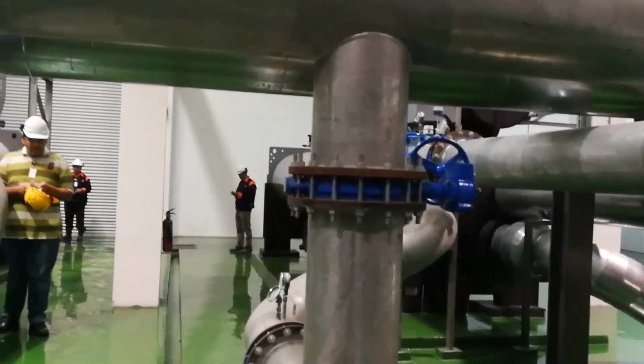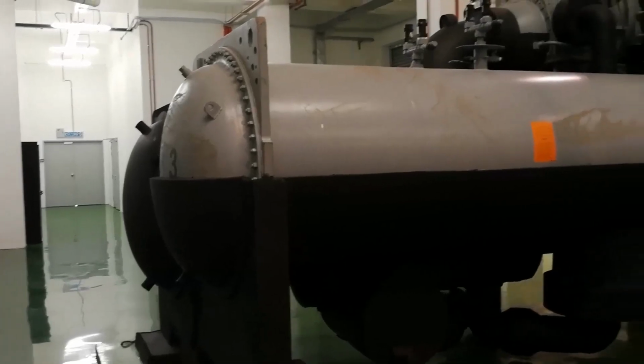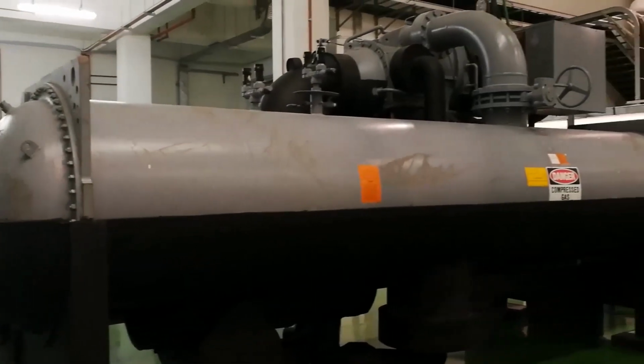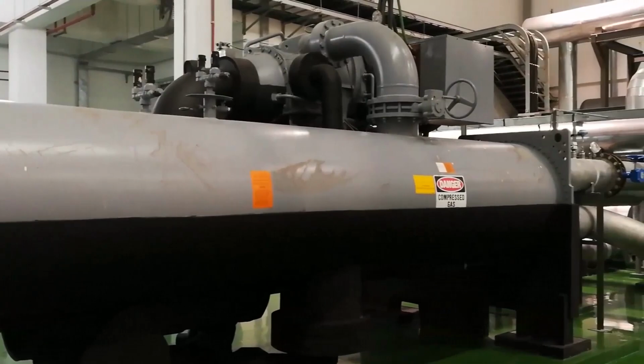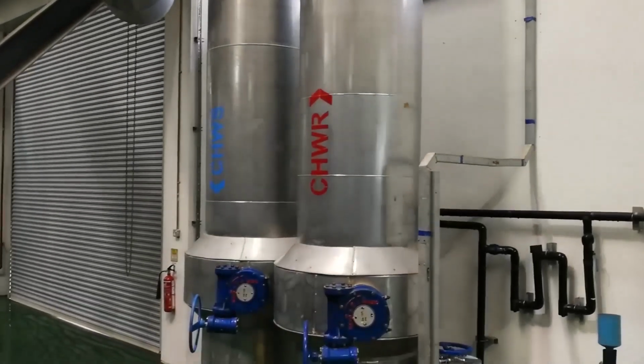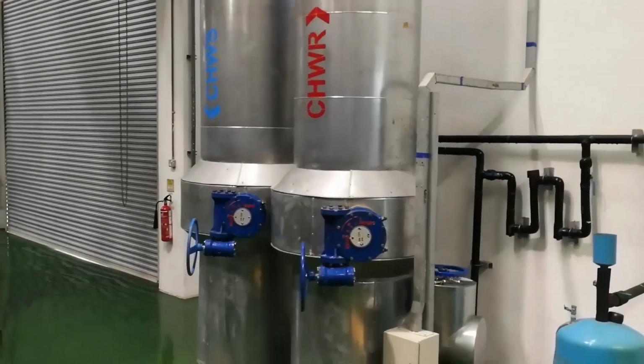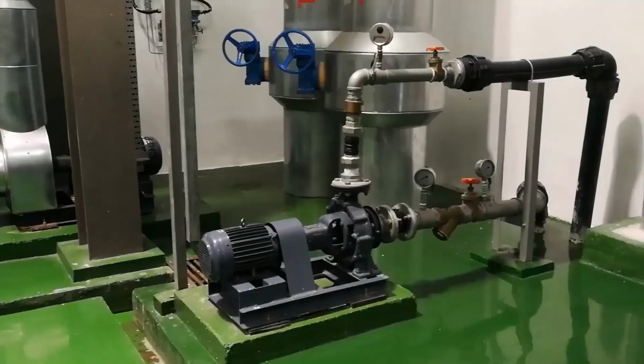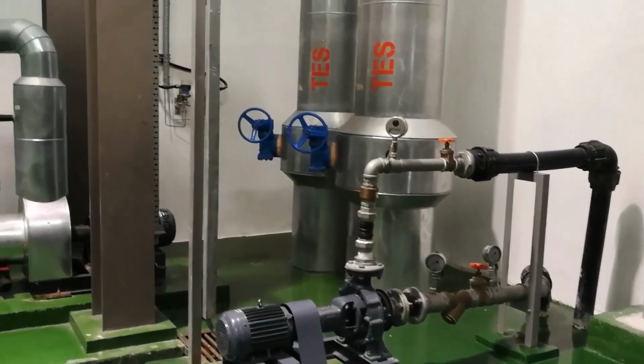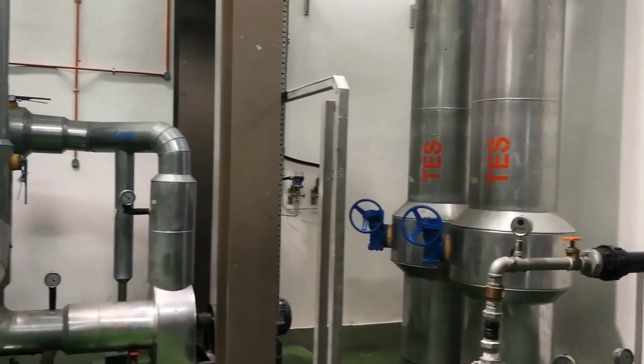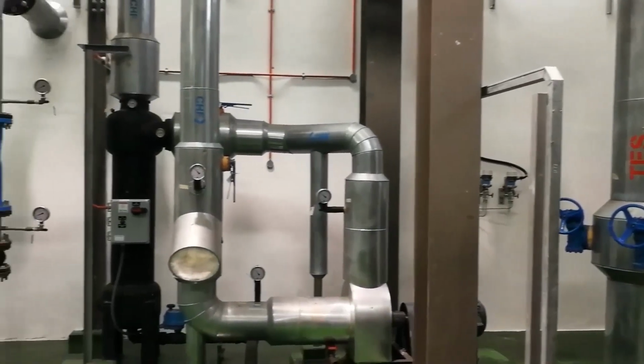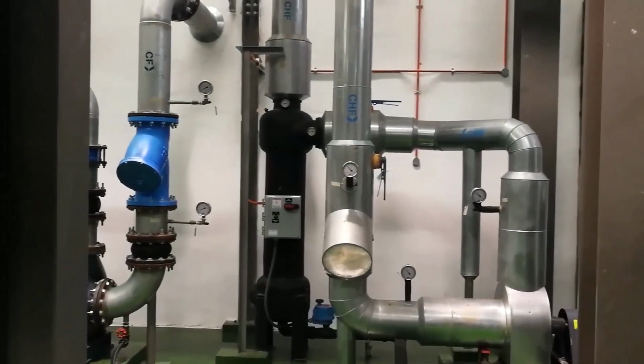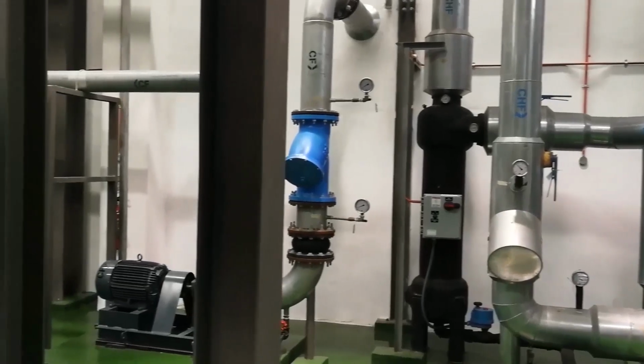Currently, for this plant, they use a process where they need to charge the TES tank at night for approximately 10 hours, making it full of chilled water at 5 degrees Celsius. In the morning, they discharge the TES tank and supply the chilled water to all institutions, so they don't need to run the chiller because the demand is not yet maximized.